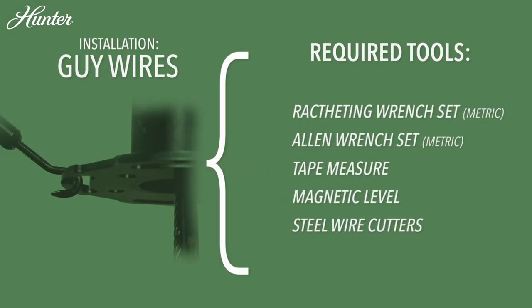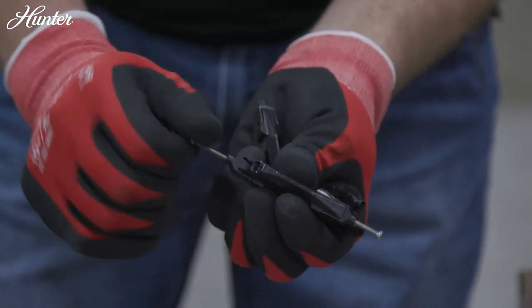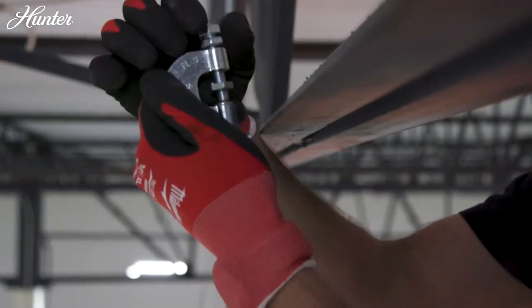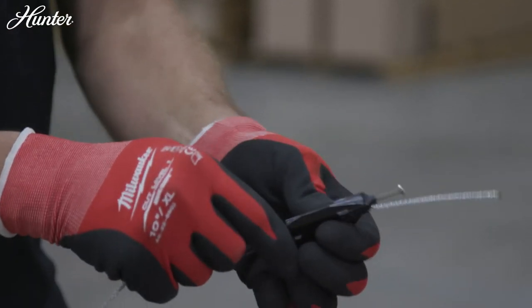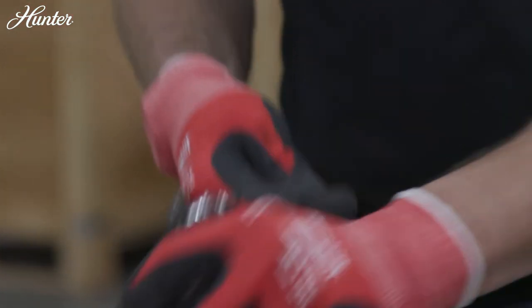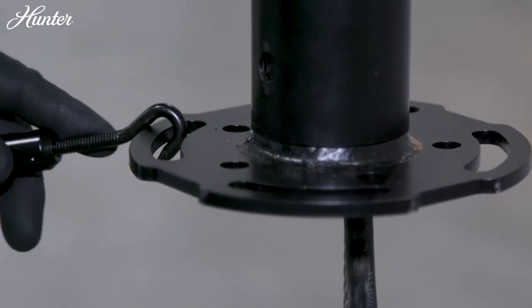For guy wire installation, begin by loosely placing the provided gripple bolts into all four gripples. Measure to ensure equal distance between the beam clamps and fan. Attach the beam clamps to the structure and tighten. Once secured, clip the 15-foot guy wire end to the beam clamp. Thread the 15-foot guy wire cable through one end of the gripple until a few inches protrude through the opposite end. Clip the end of the 2-foot guy wire to the eye bolt of the turnbuckle, then feed the opposite end through the same gripple. Hook the turnbuckle to the downrod disc.